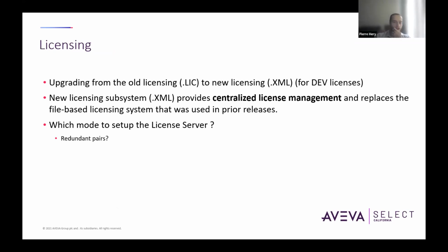Depending on how far ahead you jump in InTouch versions, you might have been using our old .lic licensing files, and the current versions use .xml files that we activate using the Aveva Enterprise License Manager. Versions up to 2014 R2, I think, are the ones that use the .lic licensing model. So if you're going from that system to .xml, you want to be aware of how the activation changes, which isn't overly complicated, it's just something to be aware of.